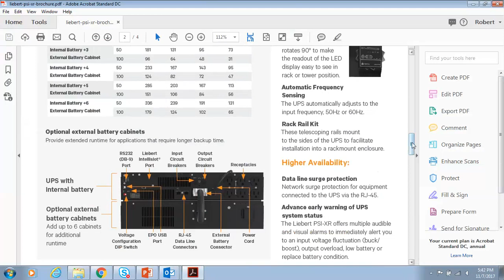Usually on any extended runtime unit, the manufacturers will tell you the type of runtime you can expect. So in this case, there's 1,000 VA, 1,500, 2,200, and 3,000. It'll tell you the runtime at half load and full load, so at 50% and 100%. That's what you're looking at here.